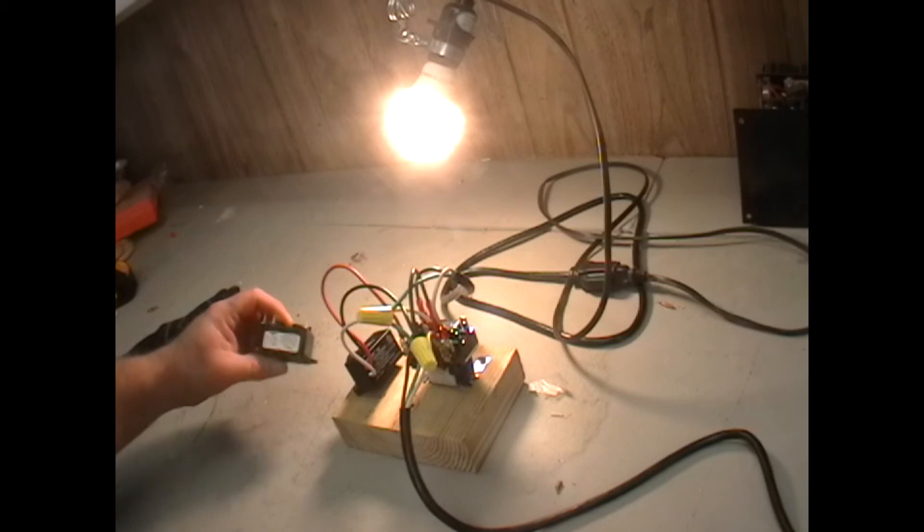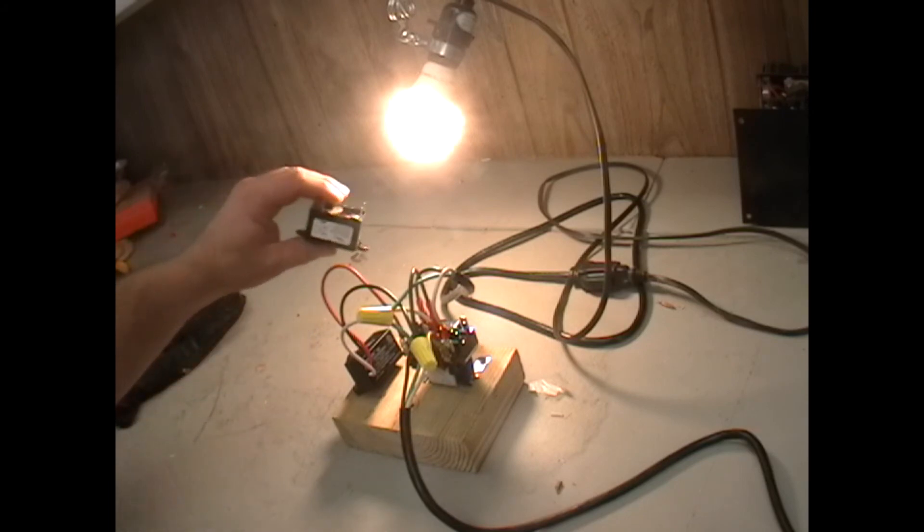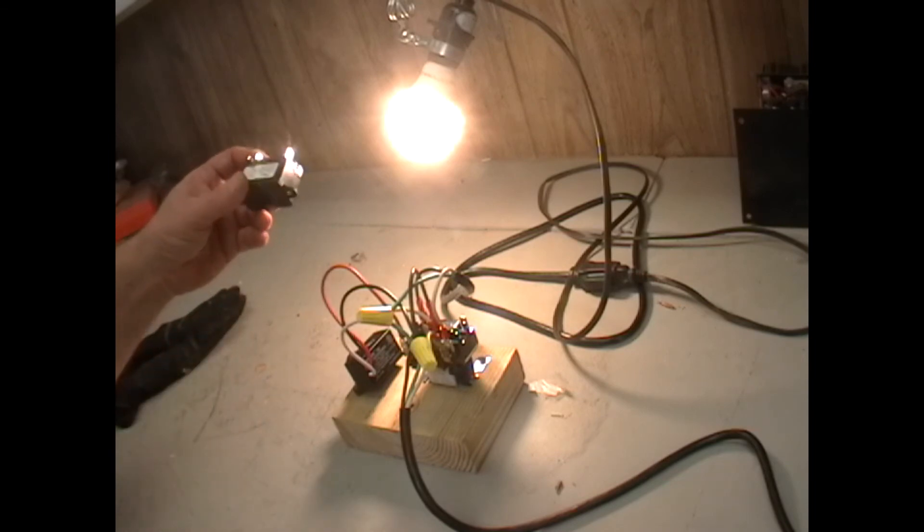Another thing to keep in mind is both of these relays, this one and this one as well, you'll have 12 full load amps, 12 FLA. That's not a lot. You're not going to run a lot of big pumps with that.